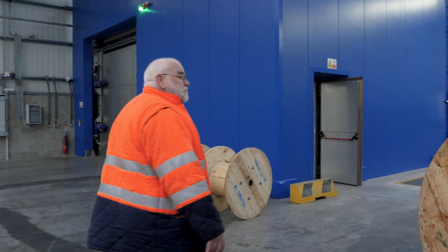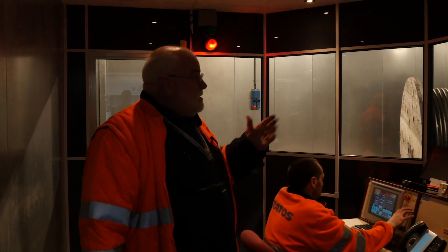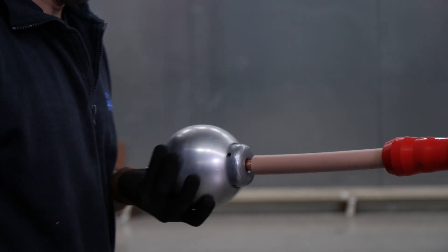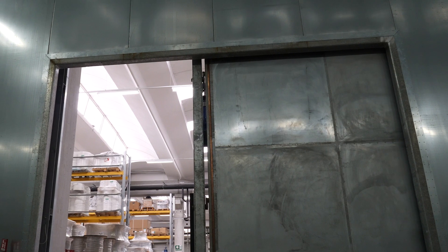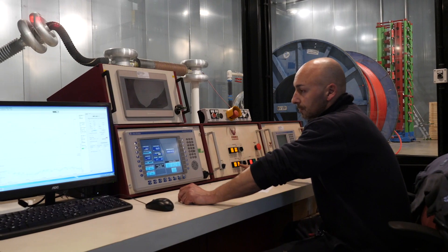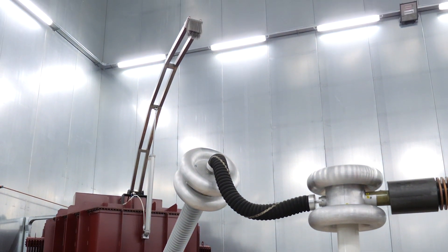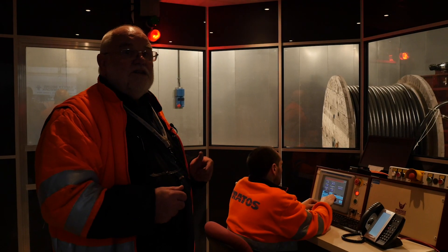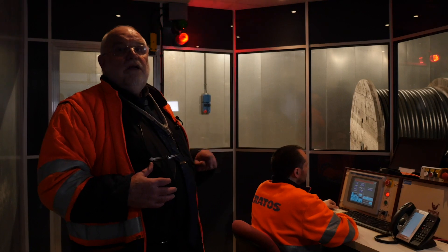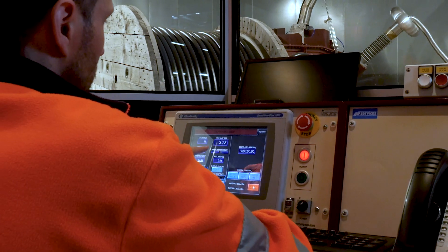Having said that, it's still an impressive piece of kit. With this test equipment, we can apply a maximum of 100 kV and the maximum power output is 5000 kVA. If we detect any discharge within this chamber, it must be coming from the cable. That's why we can be very, very confident, very sure that if we say a cable has no discharge, that's what we mean. There's no detectable discharge in it. We know that cable is sound and it's going to give a long life — it isn't going to be discharging throughout its operation and potentially failing prematurely.